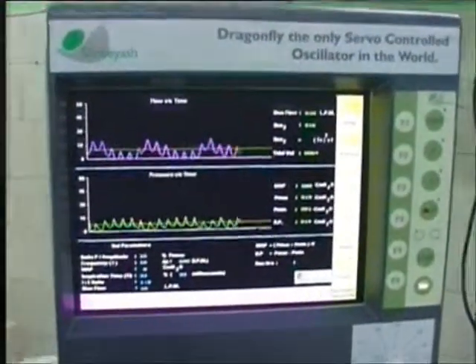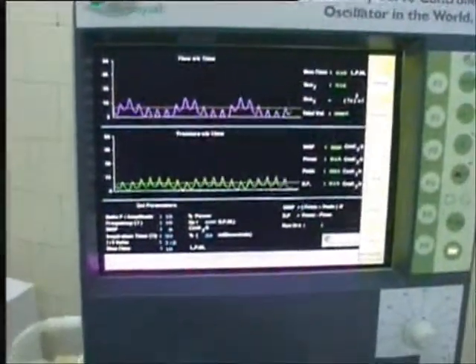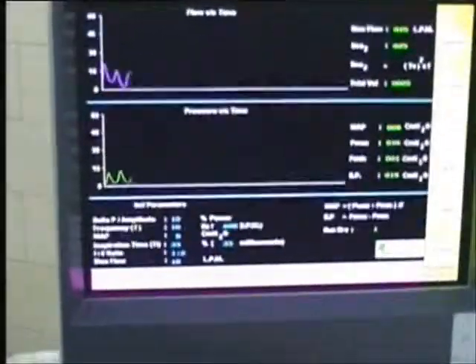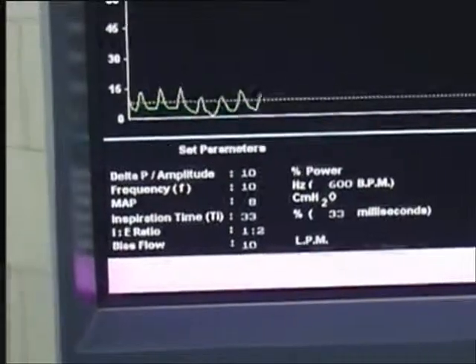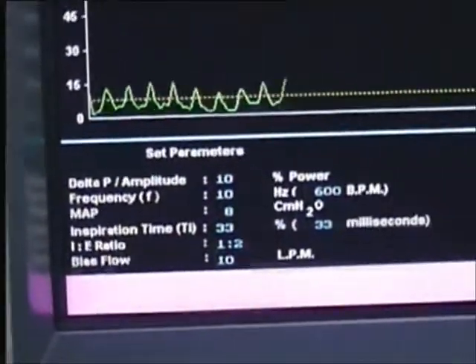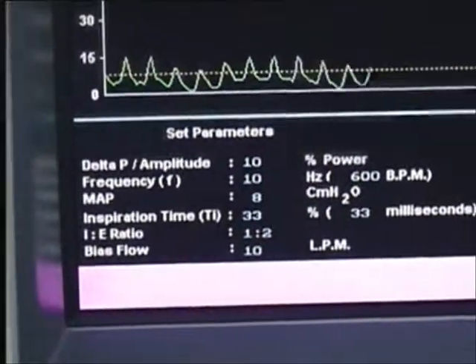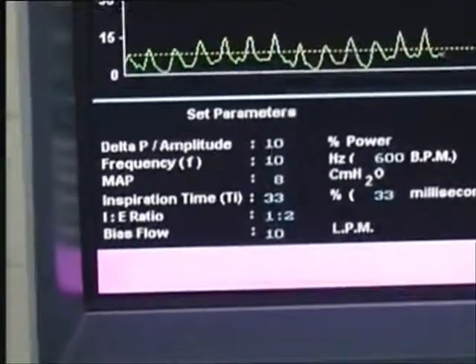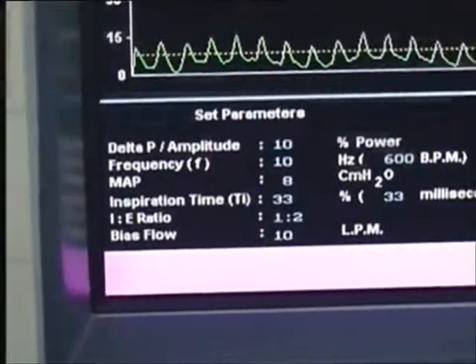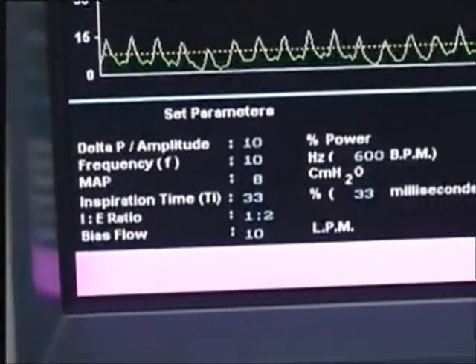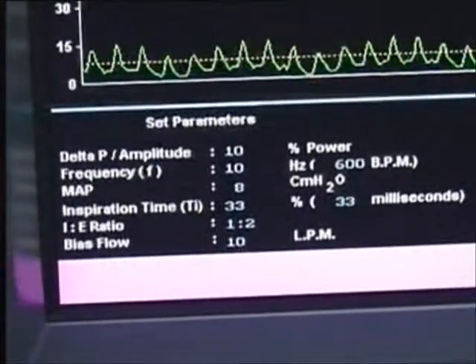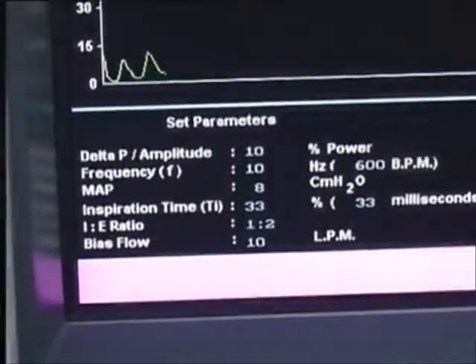This HFO is manufactured by Shreyash. The name is Dragonfly, and it is a fantastic ventilator, and you can see the waveform and the settings which we have done. We started the child on a mean airway pressure slightly higher than the MAP of 7 the child was earlier on. We started with 9, and the frequency we kept at 10 and delta P of 10. FiO2 was 60% to start with, and IE ratio was 1:3.